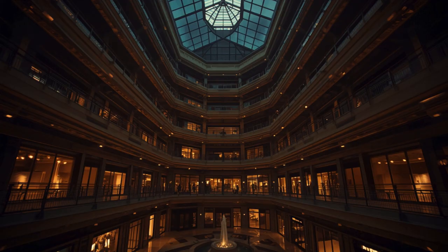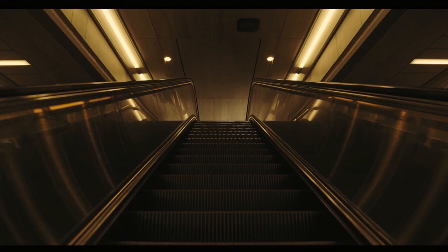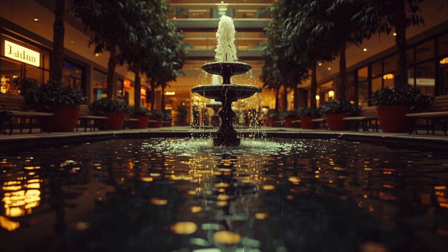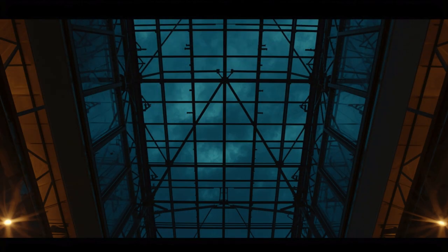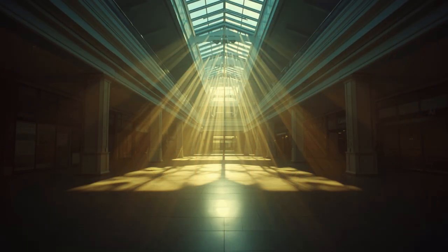In a conventional room of normal ceiling height, the temperature difference between floor and ceiling is small enough to be unimportant. In a tall atrium, stratification can produce a temperature difference of 10 degrees or more between the occupied zone near the floor and the air near the roof, with the warm air at the top being of no comfort benefit to the people at the bottom, and the solar heat gained through the skylight adding further warmth to the already warm upper zone. Managing this stratification required mechanical strategies that went beyond the simple supply and return systems adequate for lower space areas of the building.